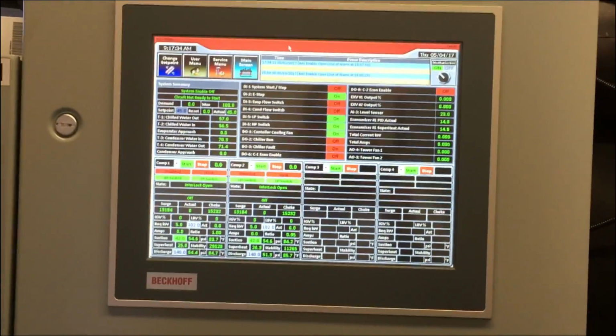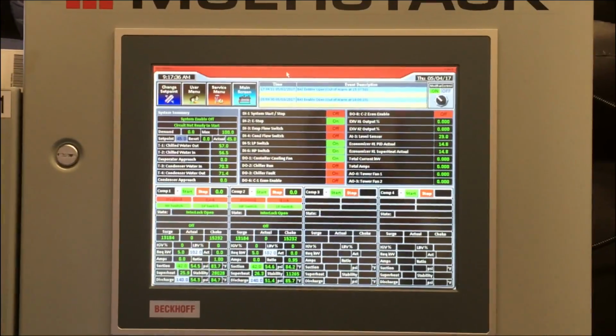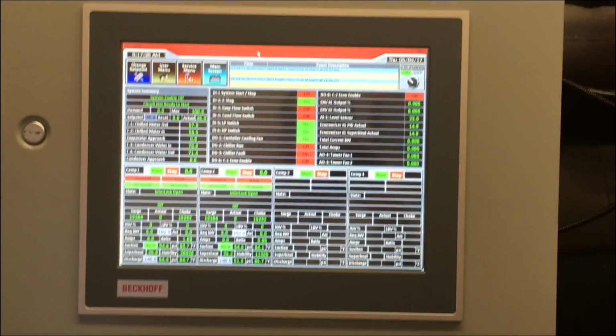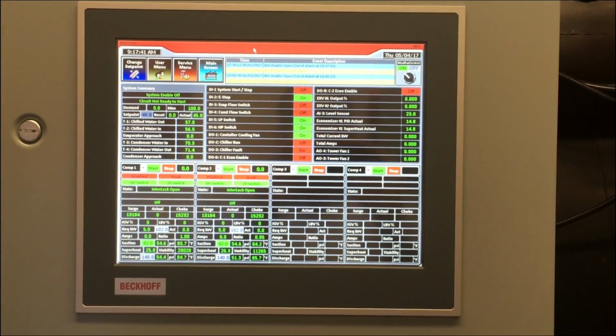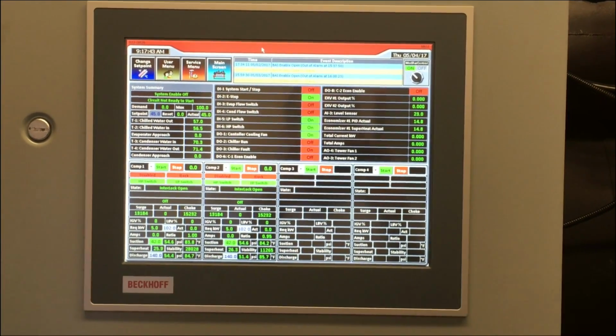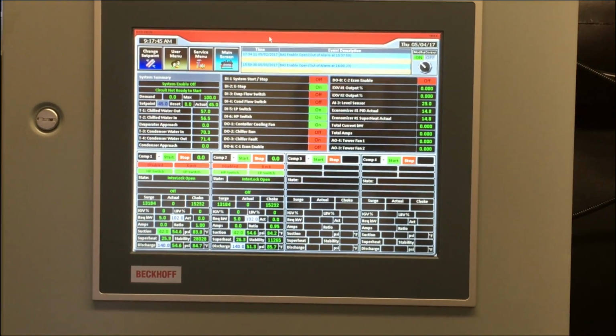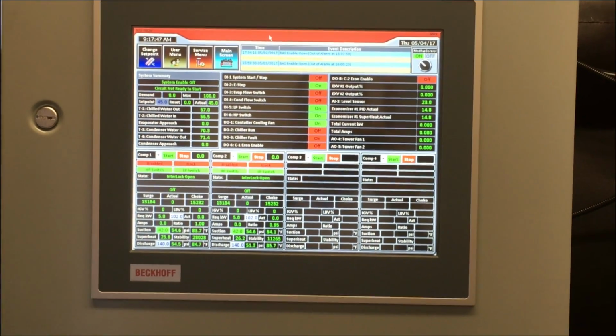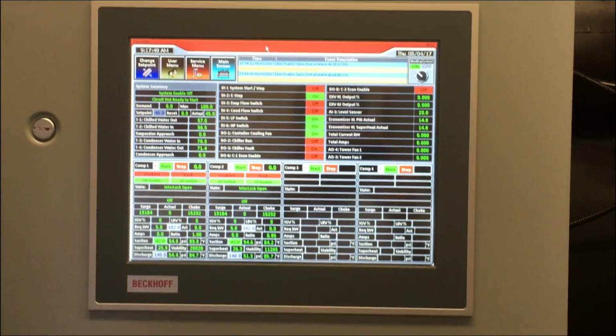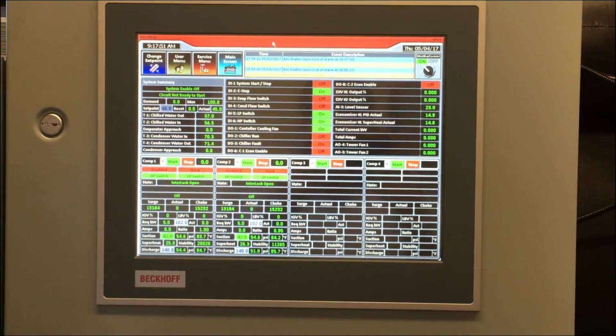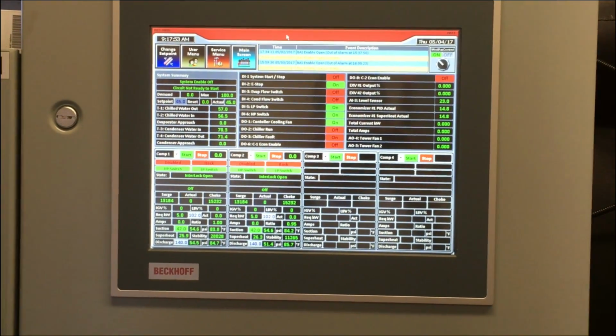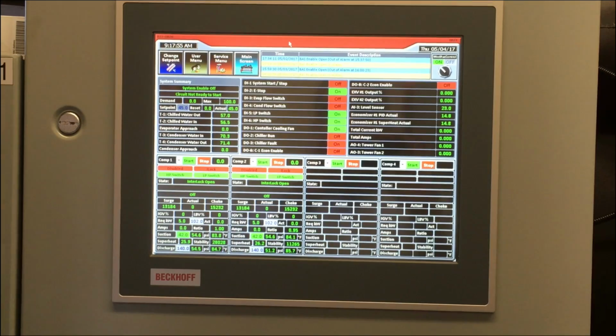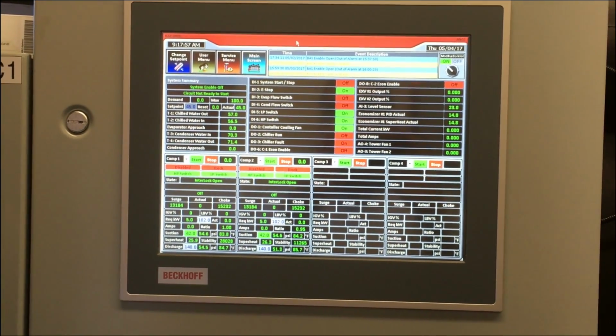So that number holds true on the condenser side too. The discharge temperature versus leaving condenser water temp would be our approach. And that should be tight also, because if that starts to spread, same thing. We're either not moving water fast enough, or we're dirty, we're not transferring heat as we should, and the heat's not being rejected and it's building up in the chiller and causing issues.